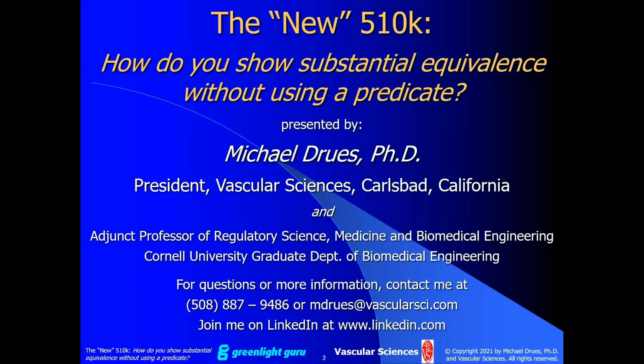Hopefully that makes sense. Yeah, and I'll just add to that a little bit, Mike. Courtney, one thing to consider, regulatory pathway aside, is that when you're going into home use, Mike's spot on, of course, with his comments on usability. Sometimes the home use environment can have other environmental impacts or influences, especially if you're dealing with a mechanical medical device. So sometimes those may trigger additional things that you need to do to demonstrate safety in that home use. So just keep that in mind too.